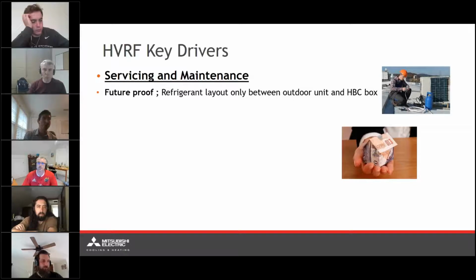From a service and maintenance standpoint, as previously said, future-proof, so we're limiting the amount of refrigerant in the system, so we're limiting the headaches involved of acquiring more refrigerant in the system, potentially having leaks downstream of the BC controller. A leak downstream of the BC controller at this point is just going to be a water leak, which isn't great, but you don't have the complicated process of brazing pipes together that potentially could be prone to leaking. You have a qualified installer, a strong installer, you're not going to really be looking at any of those types of leaks.